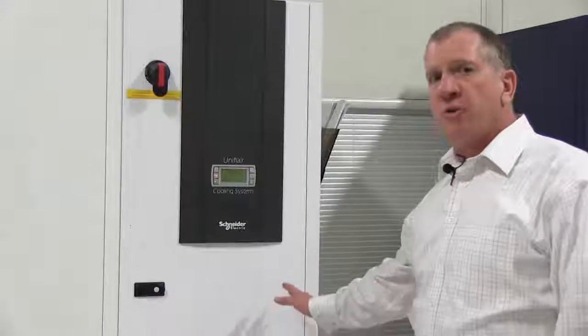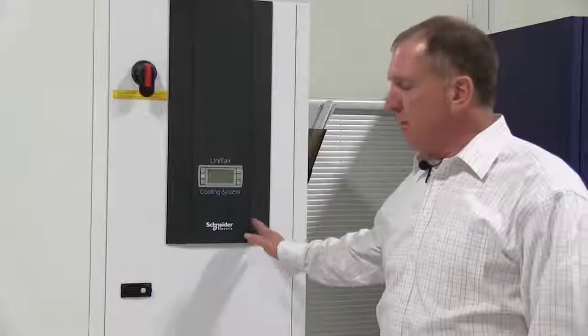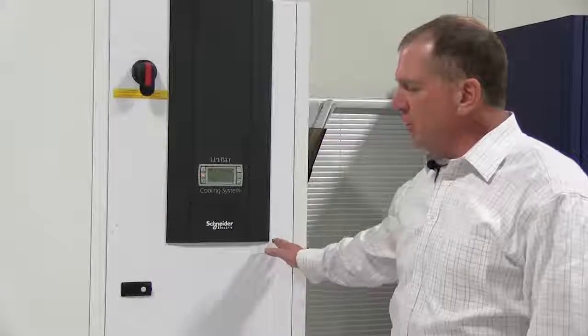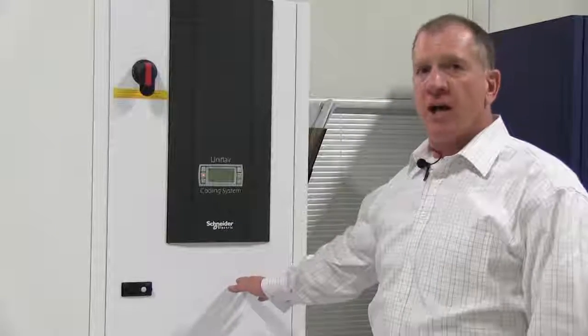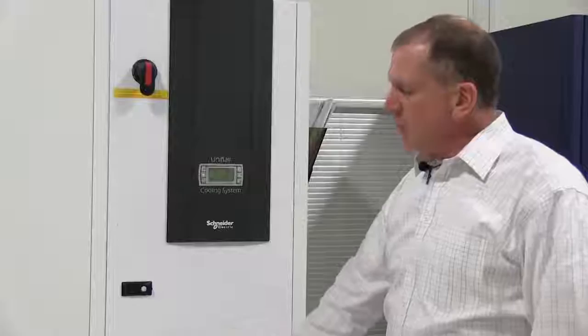Today we're in the cooling lab of our West Kingston facility to demonstrate the Uniflair room cooling units. Uniflair precision air conditioners are available in both upflow and downflow configurations. They're also available in heat rejection, chilled water with capacities up to 40 tons, and air, water, glycol economizing units with capacities up to 30 tons. This particular unit is an energy-saving glycol economizing unit. It is downflow discharge and sits on an adjustable floor stand.